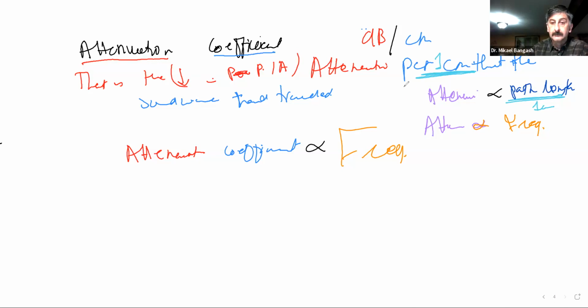But your total attenuation is directly proportional to your path length. Generally speaking, your attenuation coefficient is directly proportional to the frequency of the transducer, and the greater your attenuation coefficient, the greater will be your overall attenuation. Did you guys get that? Yep. Good.